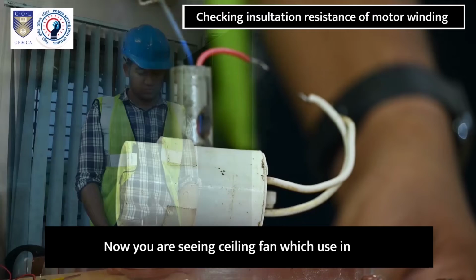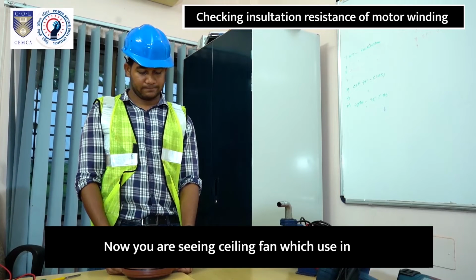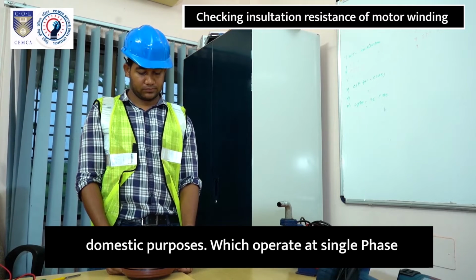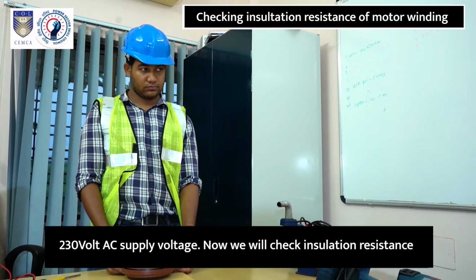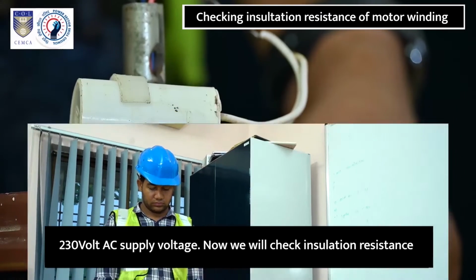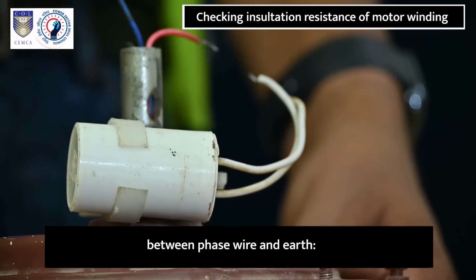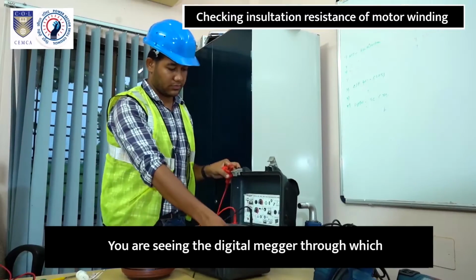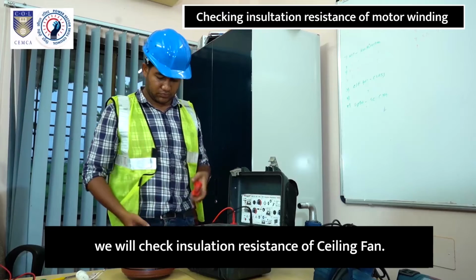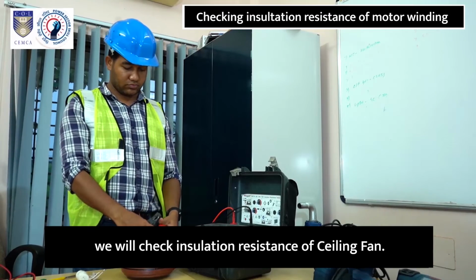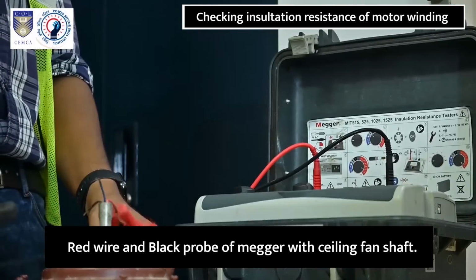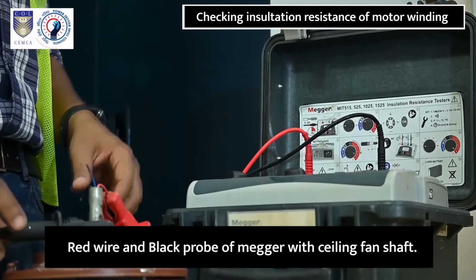Evaluate the test results. Now you're seeing a ceiling fan which is used for domestic purposes, which operates at a single phase 230 volt AC supply voltage. Now we will check insulation resistance between phase wire and earth. You are seeing the digital megger through which we will check insulation resistance of the ceiling fan. Connect the megger red probe with the red wire and the black probe of the megger with the ceiling fan shaft.